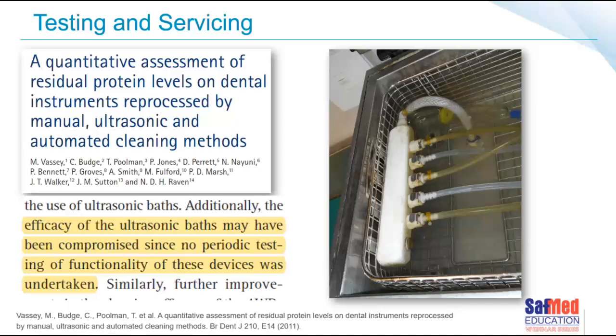Looking at the image on the right, Kurt, you and I saw that one day in the field, and we've seen this a few other times as well. Two things stand out for me. One is the actual color of the tubes themselves, so I'm assuming that tubing is quite old and looking terrible. But also the buildup of gunk on that white manifold is incredible. It looks to me like a mold or a fungus that's grown.